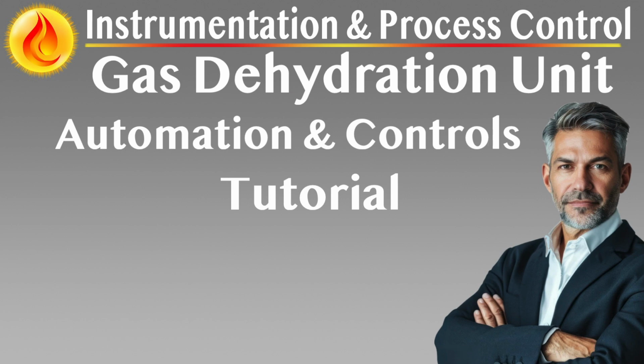Pressure high trip, PZTHH, initiates automatic system shutdown to protect the column and downstream processes from overpressure. Gas inlet temperature monitoring. Resistance temperature detector, RTD, or thermocouple, TC, at the gas entry point is monitored to prevent hydrate formation and aid in determining optimal lean glycol feed temperature.